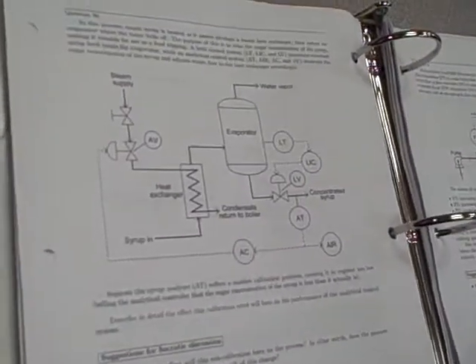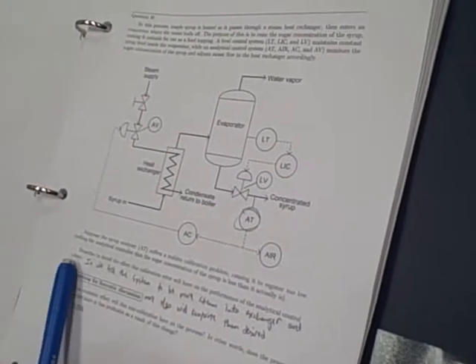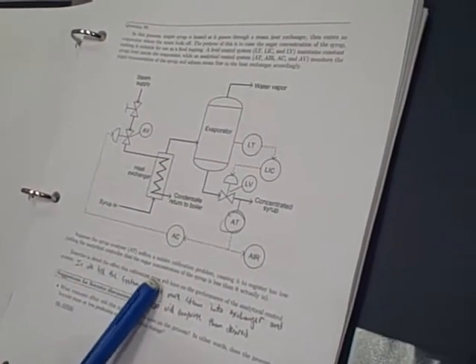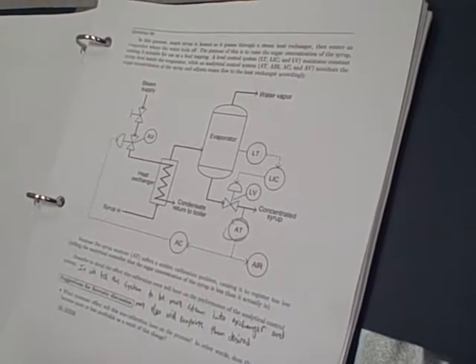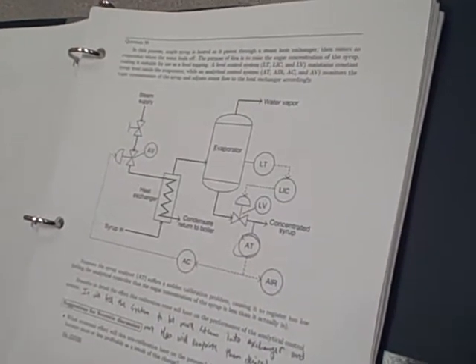Alright, so number 90. Suppose a syrup analyzer suffers a sudden calibration problem causing it to register too low, telling the analytical controller that the sugar concentration of the syrup is less than it actually is. Describe in detail the effect of this calibration error on the performance of the analytical control system.